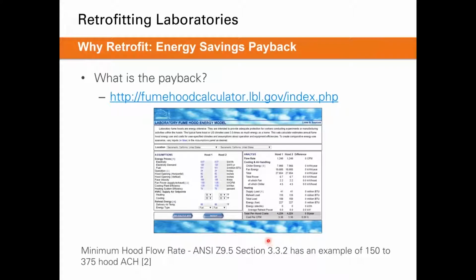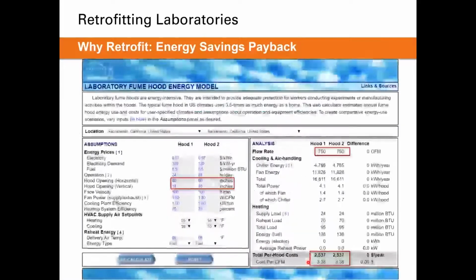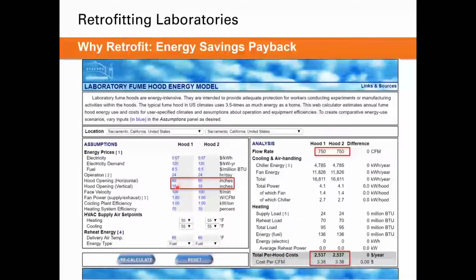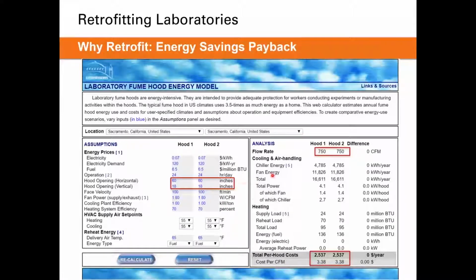So for my example, I'm going to be using a certain CFM flow rate as the minimum, and I grabbed that from the ANSI Z9.5 section 3.3.2. It states, as an example, for a hood air change rate between 150 and 375, and based on the hood dimensions, that's how I got my minimum CFM. So this is the example of a constant volume hood. What I've put in the parameters here is a 5-foot wide hood being run 24 hours a day with a sash open height of 18 inches. That came out to about 750 CFM for the flow rate. And I didn't change this sash height because it would affect the CFM output, but we can say for the CV example, we know that it's always going to be exhausting 750 CFM. And then the total cost to run this hood per year would be $2,500.